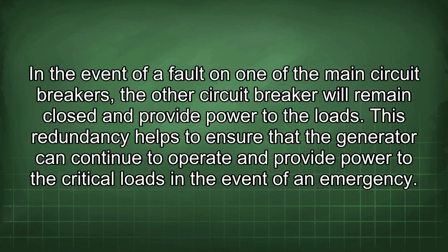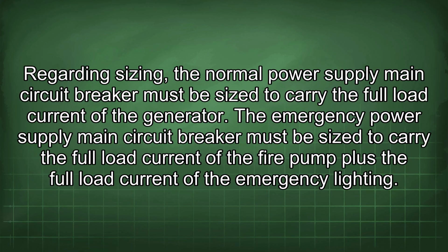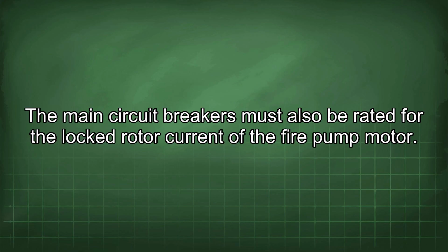In the event of a fault on one of the main circuit breakers, the other circuit breaker will remain closed and provide power to the loads. This redundancy helps to ensure that the generator can continue to operate and provide power to the critical loads in the event of an emergency. Regarding sizing, the normal power supply main circuit breaker must be sized to carry the full load current of the generator. The emergency power supply main circuit breaker must be sized to carry the full load current of the fire pump plus the full load current of the emergency lighting. The main circuit breakers must also be rated for the locked rotor current of the fire pump motor.